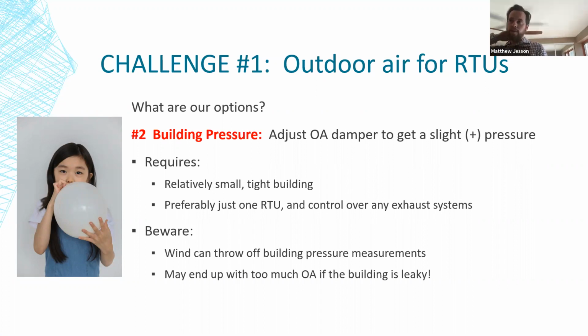Other things to watch out for: if it's a windy day, those building pressure measurements can be skewed quite a bit. And also, if your building is pretty leaky, this could end up giving you too much outdoor air, and then of course giving you capacity problems on your rooftop unit. So hopefully with an experienced TAB technician, that would be fairly obvious if they're trying to do this. If you're trying to pressurize a small building with your rooftop unit outdoor air, and you're opening it up, and you're like, okay, hey, there we go, I finally have a slightly positive building, and my outdoor air damper is wide open for minimum outdoor air. That should be a red flag.